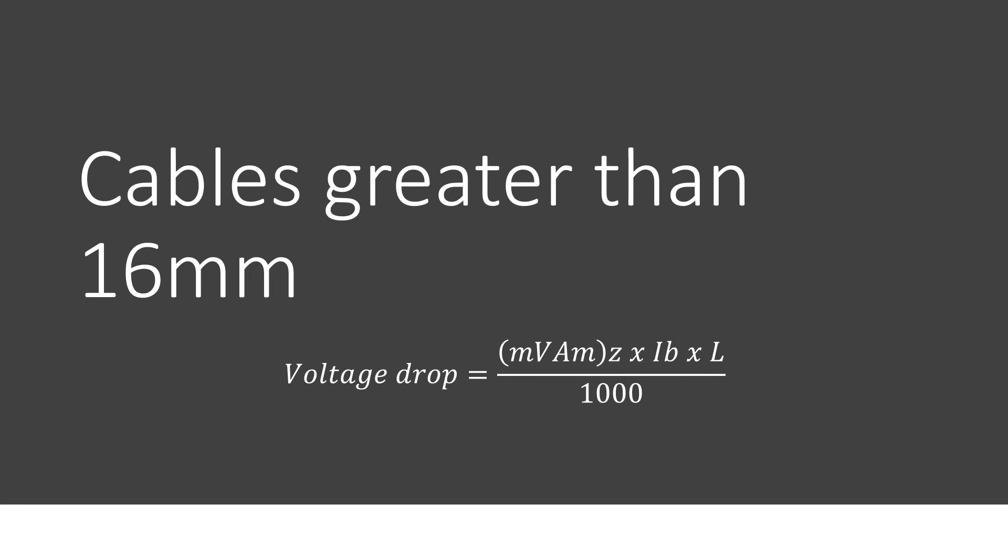For other cables, you will notice that where cables are larger than 16mm, there are three values for millivolts per ampere per meter and these are listed under the headings R, X and Z. R is for resistive and X is for reactive. So where the power factor is not known and we're using a cable that's larger than 16mm, we use the value for millivolts per ampere per meter Z.